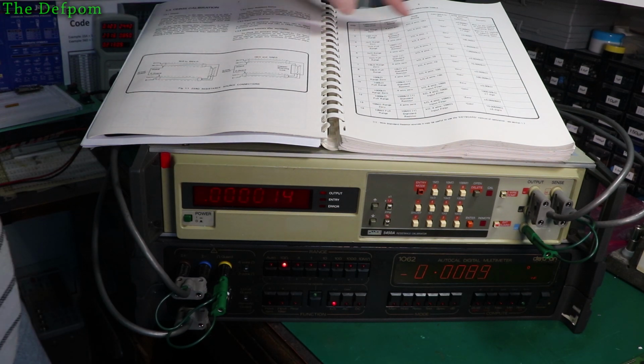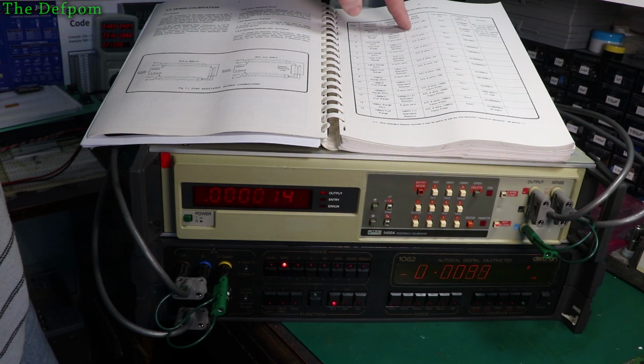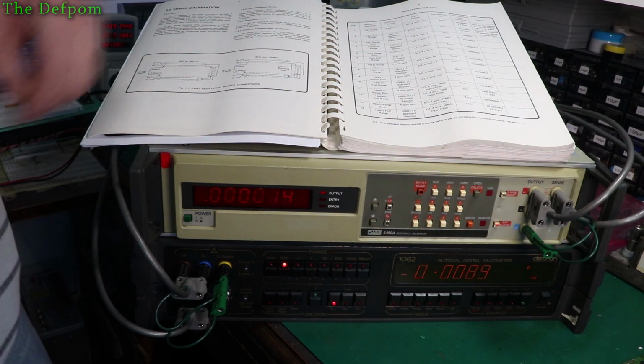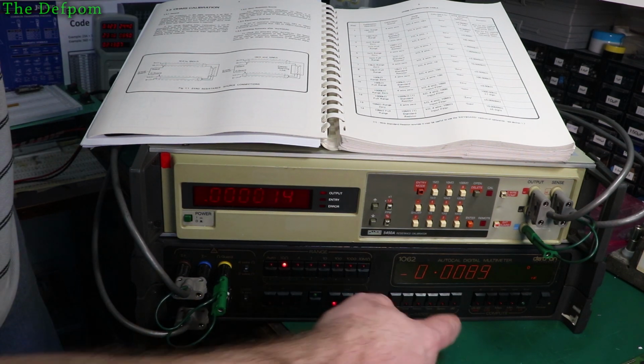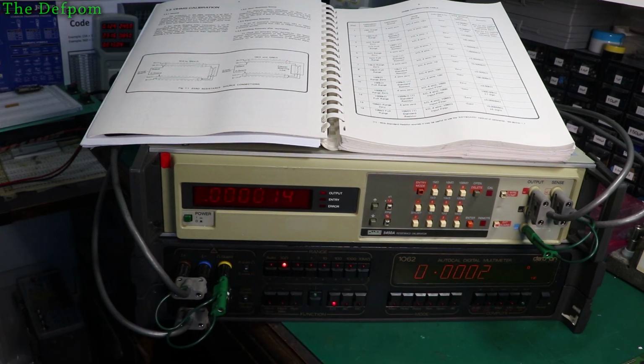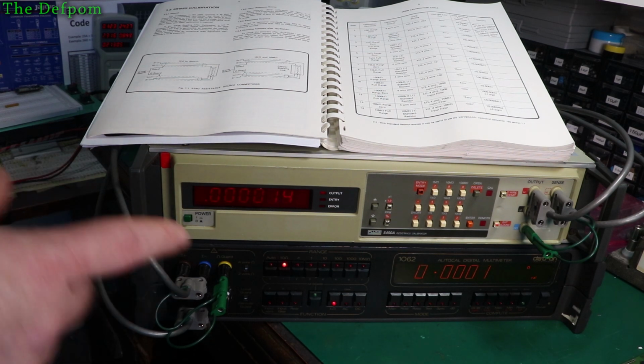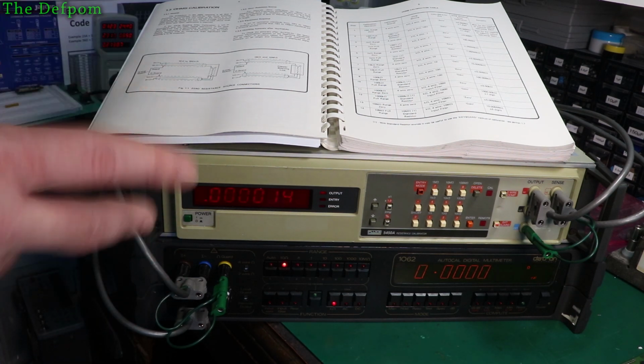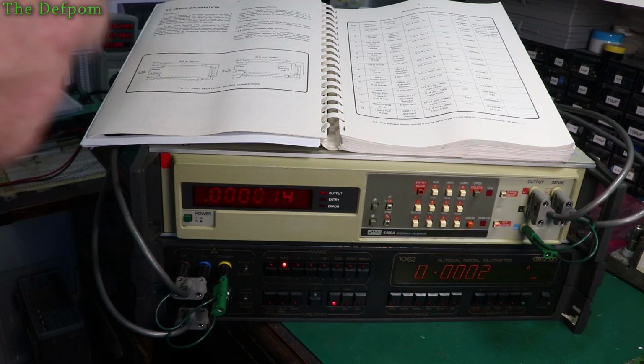If you look at this chart, it tells you what settings to use: ohms, 4 wire, and calibrate key is 0, which is down here, calibrate 0. Each time you push it, it gets closer, or if you need to refine the value, you can push it multiple times - you don't just have to do it once.